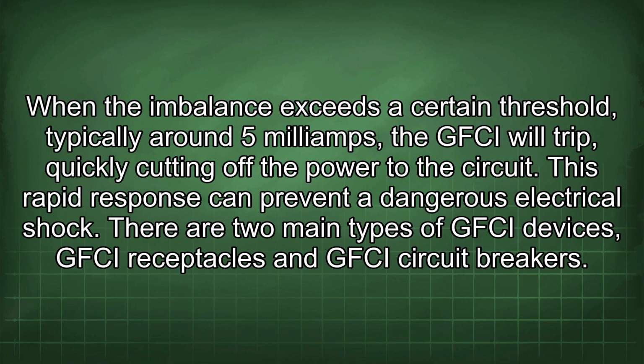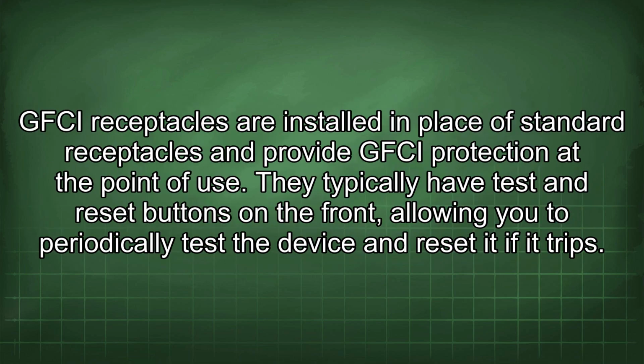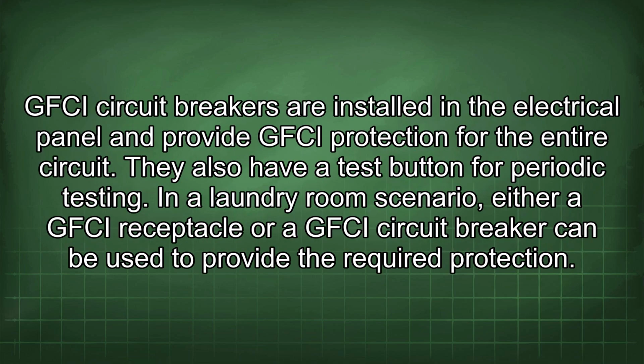There are two main types of GFCI devices: GFCI receptacles and GFCI circuit breakers. GFCI receptacles are installed in place of standard receptacles and provide GFCI protection at the point of use. They typically have test and reset buttons on the front, allowing you to periodically test the device and reset it if it trips. GFCI circuit breakers are installed in the electrical panel and provide GFCI protection for the entire circuit. They also have a test button for periodic testing.